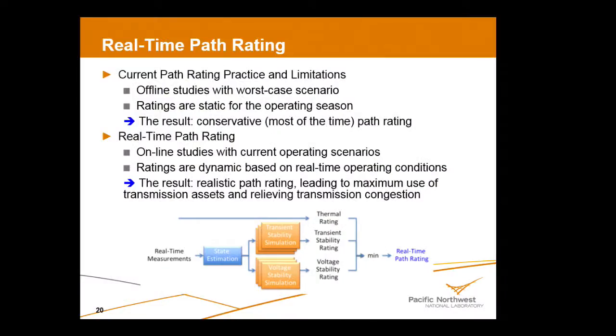Looking at today's NERC standard, in order to calculate the transfer limits of transmission lines, we have to consider 3 types of limits: thermal limit, the thermal capacity, voltage limit, and stability limits.